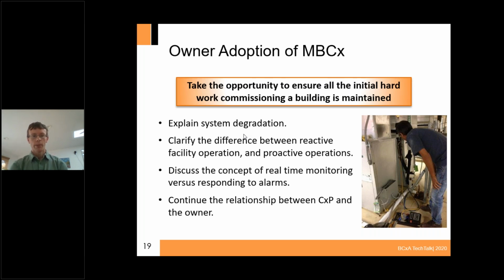So we want to take the opportunity to ensure that all the hard work you've done commissioning a building is maintained. It always seems a shame to me when I walk away from a building that probably within 6 months to a year, things aren't going to be operating as we left them. I've had buildings we've had to go back to like 7 years down the line, because the owner said nothing's working now, and it's such a shame as we walk in and discover almost every actuator, none of the valves are working right, everything's overridden, the energy use has skyrocketed, and the equipment is failing. So we really want to avoid that.